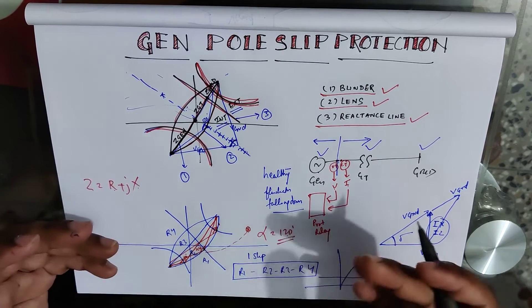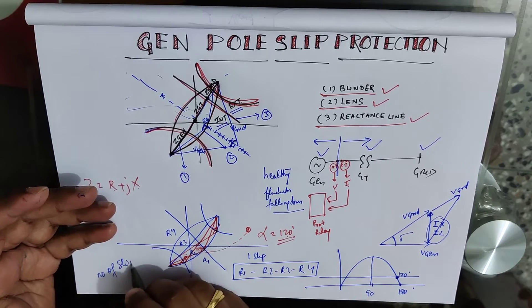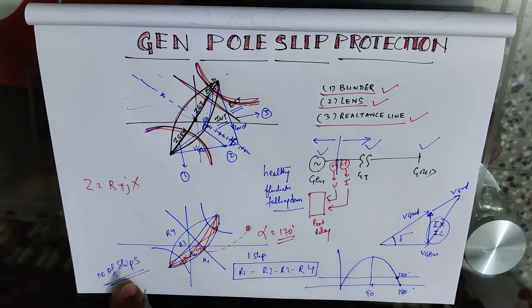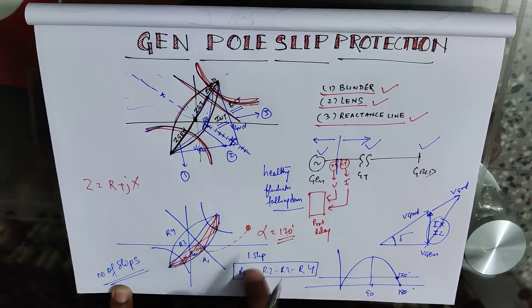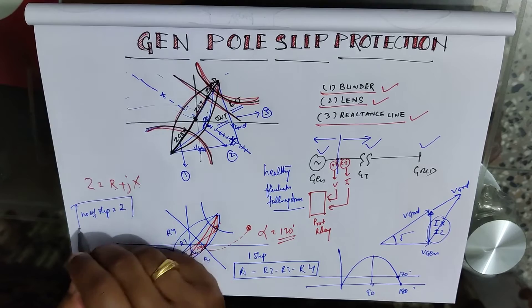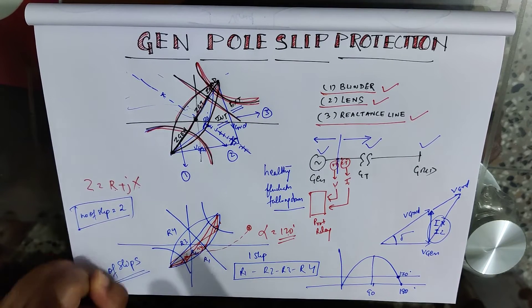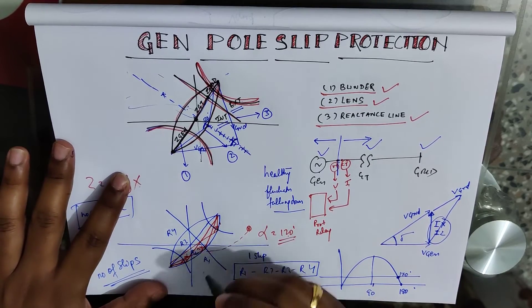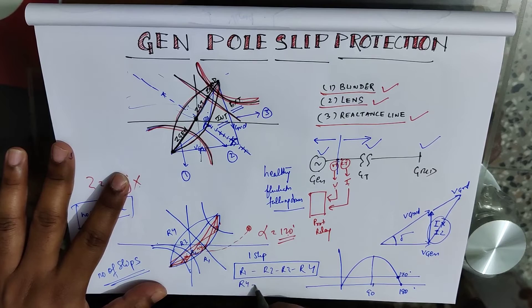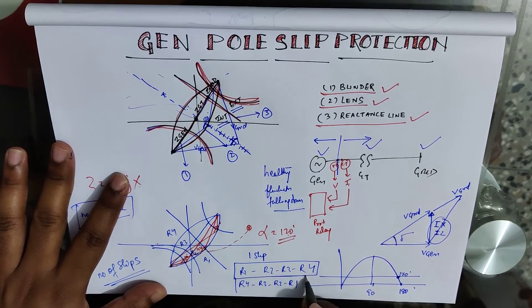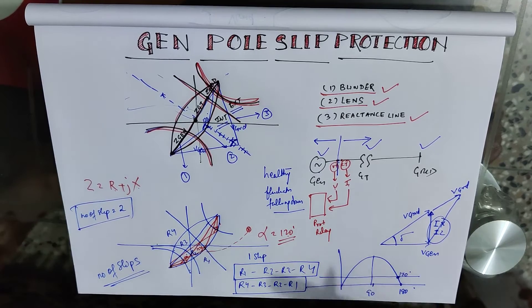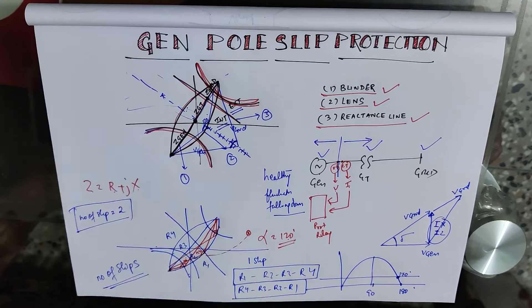Inside the relay there are settings for the number of slips. If the slips counted by the relay become equal to the setting, then only will it issue a trip command. For example, if we set the number of slips equal to 2, the relay will detect two slips — one traversal from R1 to R2 to R3 to R4, and another in reverse from R4 to R3 to R2 to R1 — and then issue a trip command. This is the logic behind the protection relay.